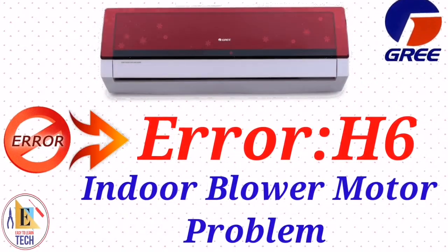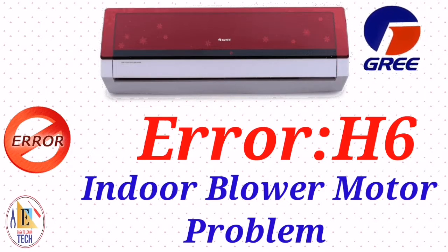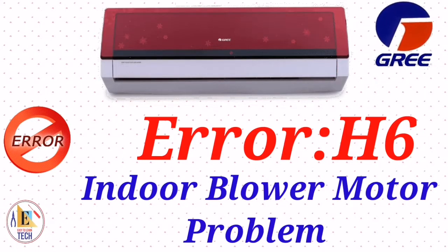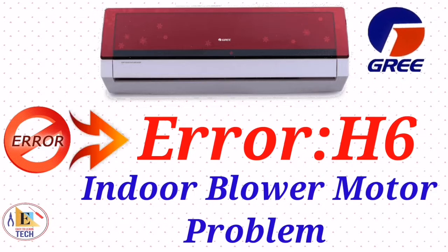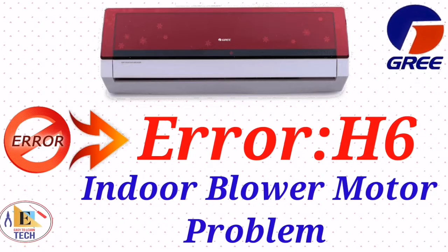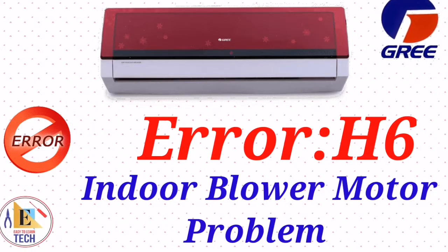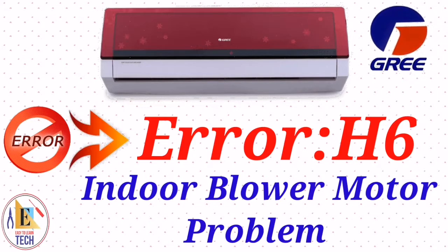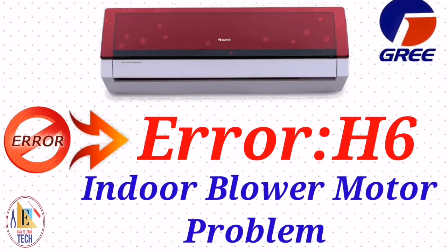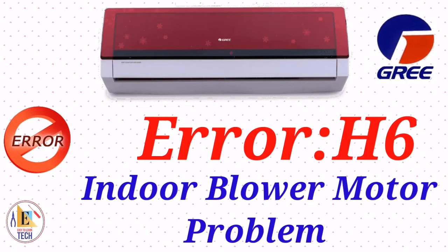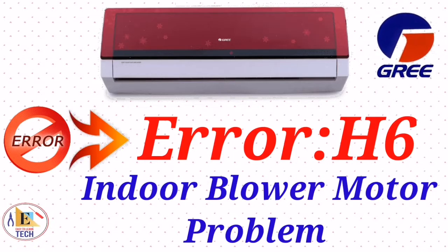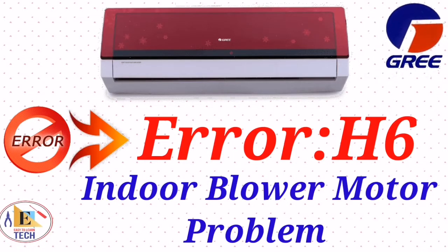See the next error code. When you see the error H6, it means indoor blower motor problem. First of all, you have to check if the blower is rotating smoothly by using the screwdriver. Rotate it once and see if our blower is rotating smoothly. If it is rotating smoothly, it means our blower is free. Then you have to check the connection of our indoor PCB for the fan motor. If the connection is not good, connect it properly and start the unit.